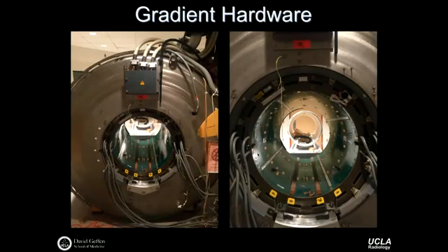And those are actually, I guess in this case, the Y gradient coil. So you can make out a saddle shape that's about here over to this side. And then there's another saddle-shaped coil that's on the top up here as well. And that's going to be one part of the Y gradient. The other end will be at the foot end. So you can just begin to make out the cable windings for that.